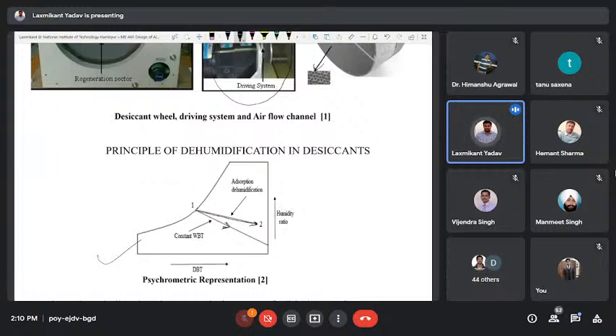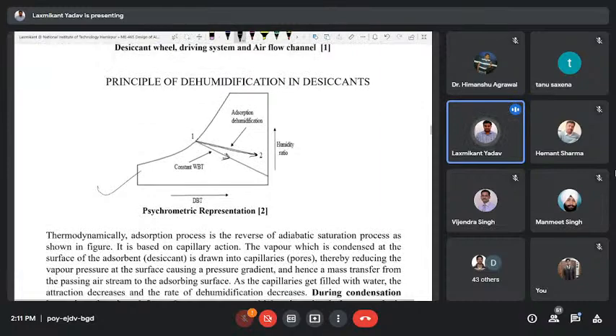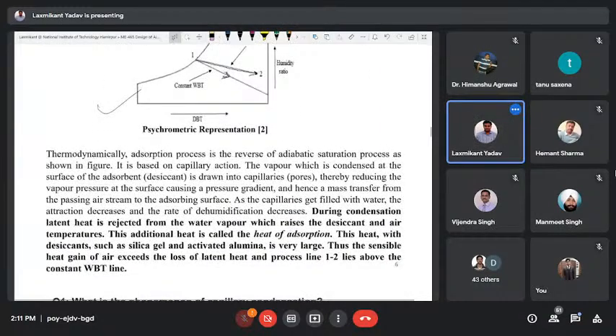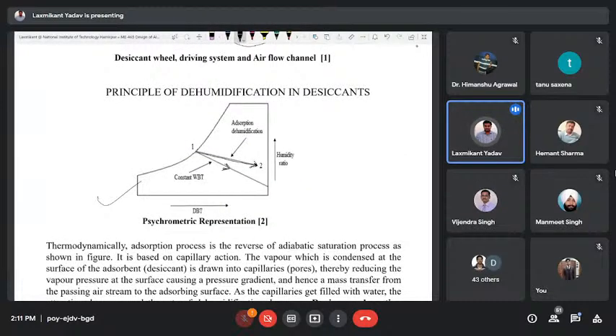Heat of adsorption, as I have already told, is the heat released during condensation of vapor into the pores of the desiccant. That heat is very high in the case of silica gel and activated alumina, and due to this, the gain in sensible heat is higher than the latent heat. During condensation, latent heat is rejected from the water vapor, which raises the desiccant and air temperature. This additional heat is called the heat of adsorption. Thus, the sensible heat gain of air exceeds the loss of latent heat, and process line 1-2 lies above the constant wet bulb temperature line. Due to this, its performance also decreases.